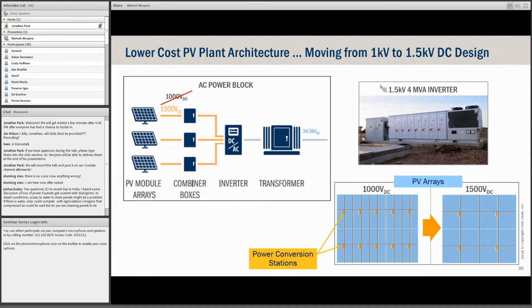Usually I ask people to look at two arrays: one is 1000 volt DC on the left, the other is 1500 volt DC on the right, which has the same amount of PV arrays in terms of PV modules. Which one do you think would have less cost? Most people would say the one on the right has lower cost because the number of power conversion stations is fewer, the roads are fewer, it's a simpler design, etc. And that's indeed the case.